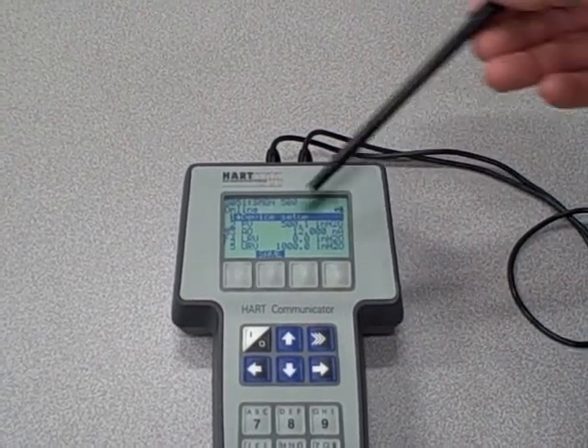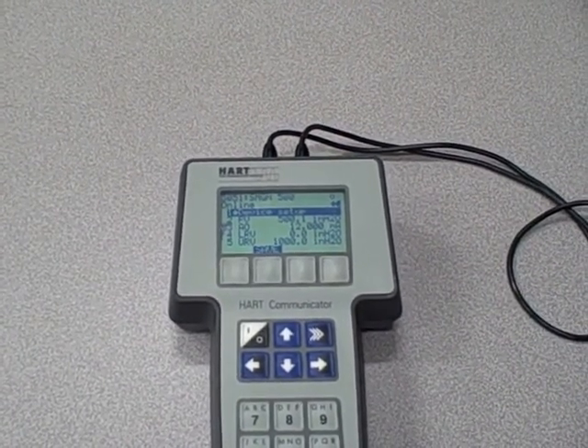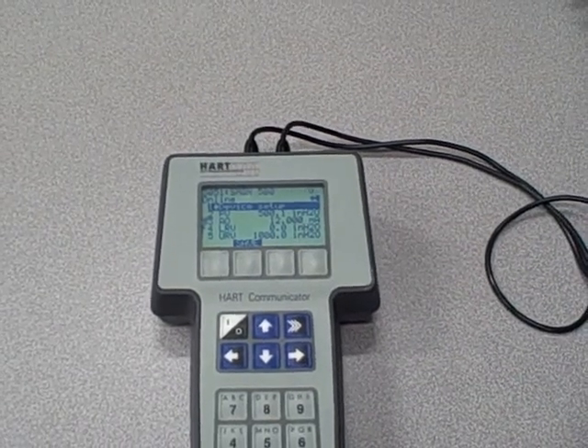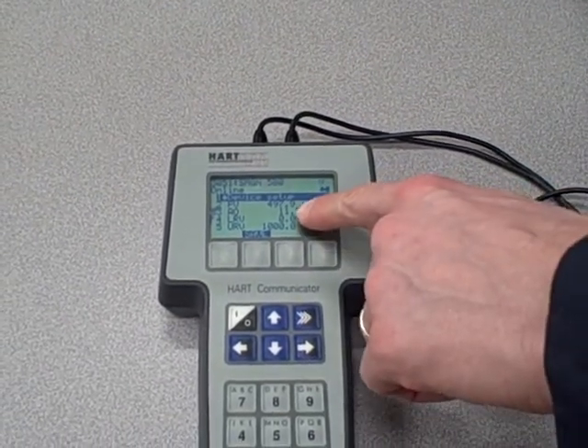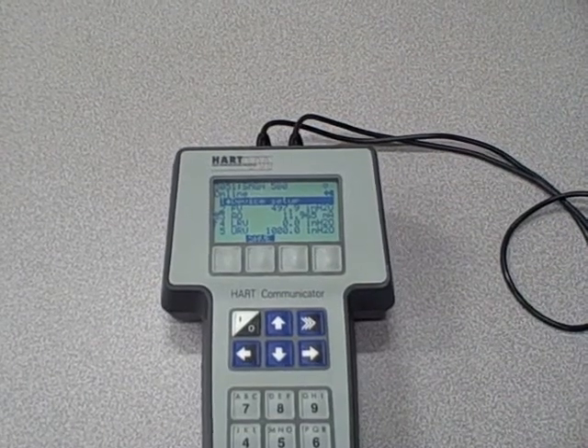It's reading the 12 milliamps, reading the 500.1 inches of water column. If I change my pressure over here, my hand pump, you can see the numbers are updating and changing, so we do indeed have a live signal.